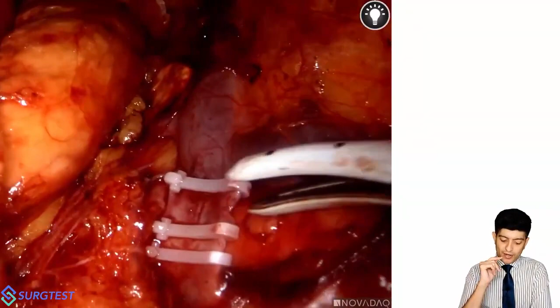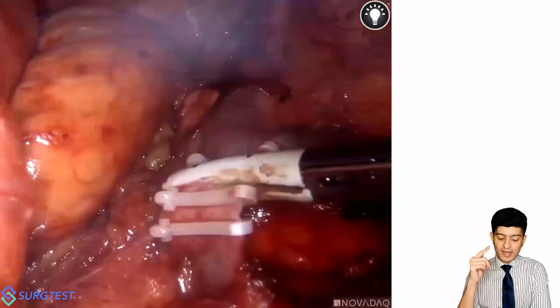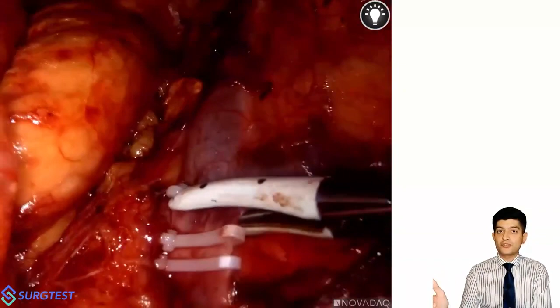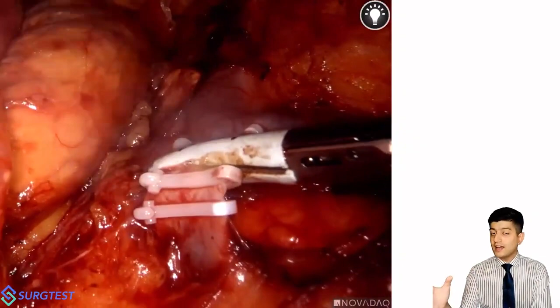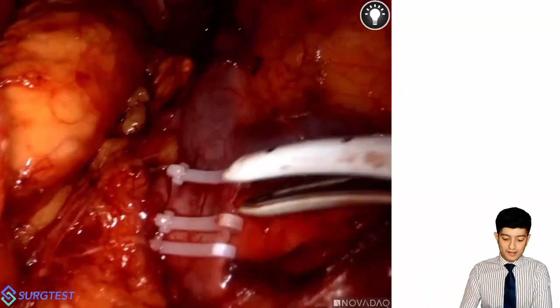So the peculiar point that I want you guys to note is once I start firing the energy, the steam that you see coming out from the area actually has a pulsatile nature. Even the bubbles start and stop intermittently, which means that despite me keeping the device button pressed at all times, the device on my behalf is shutting the energy, or rather is turning the energy on and off, ensuring that the temperature within the tissues does not rise beyond a certain level. It doesn't want the tissues to get vaporized. It wants the intima to become extremely sticky and adhere to the opposite side, have good cross bonding between the protein molecules to give you an effective vessel seal.